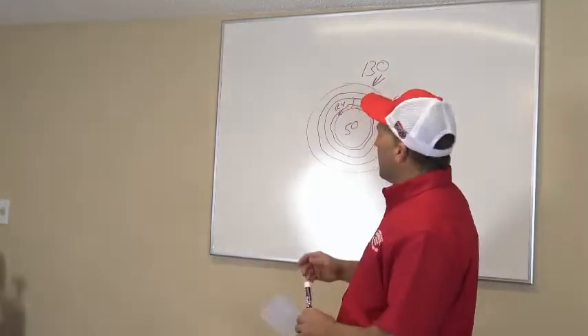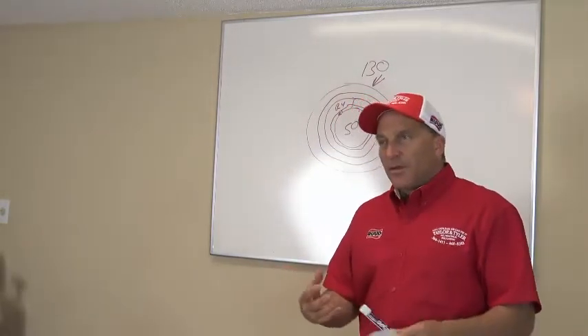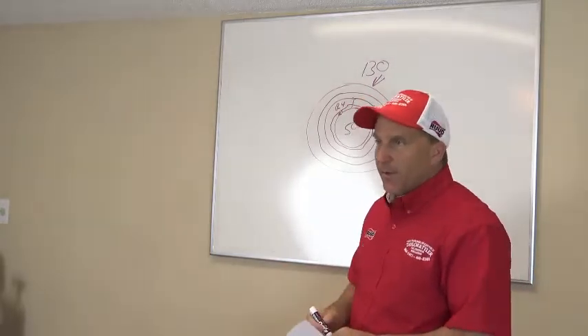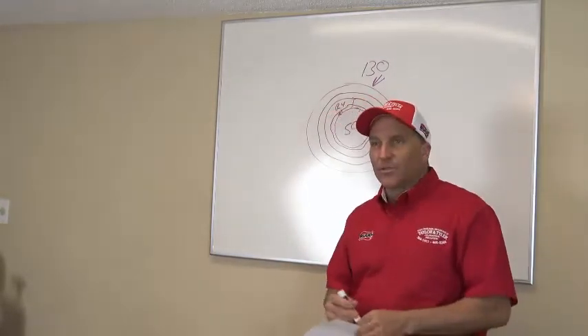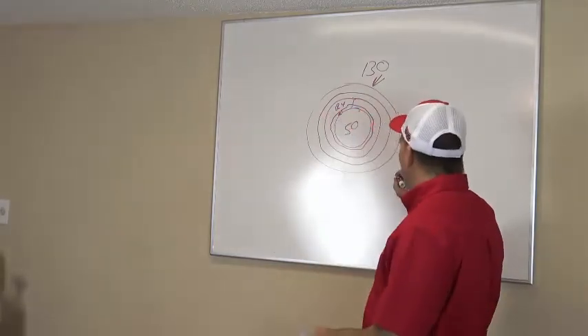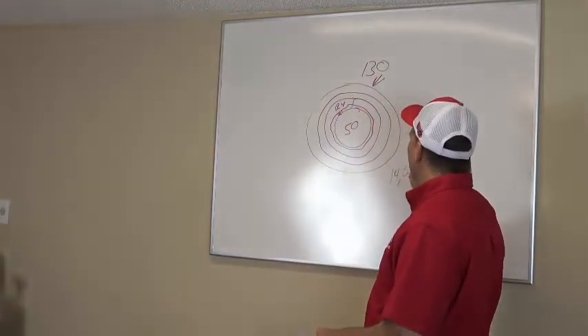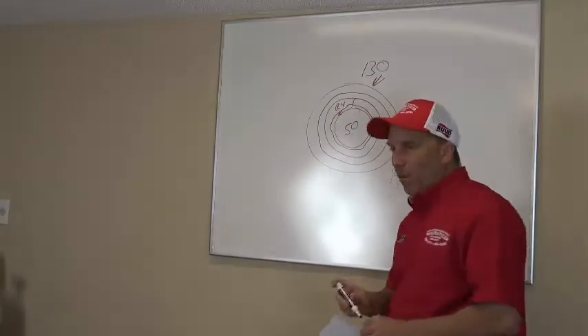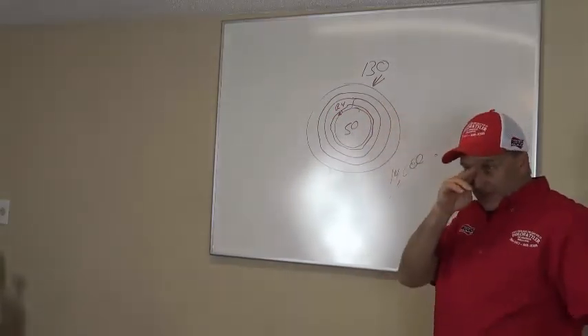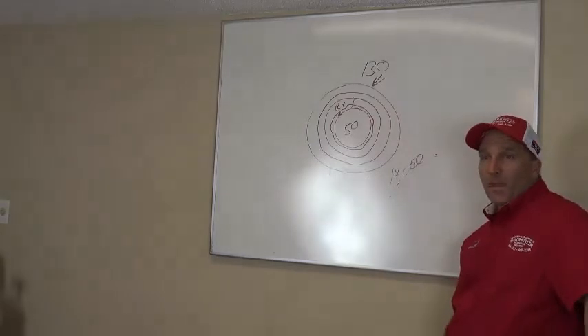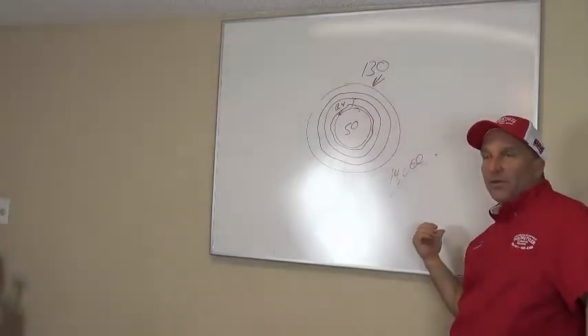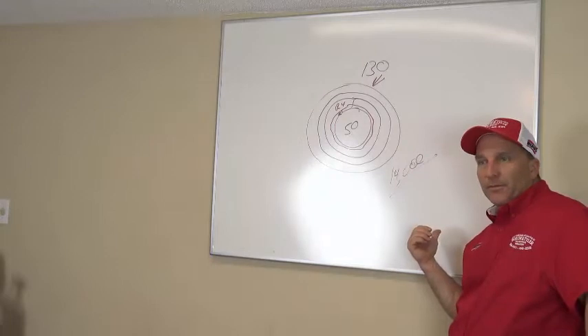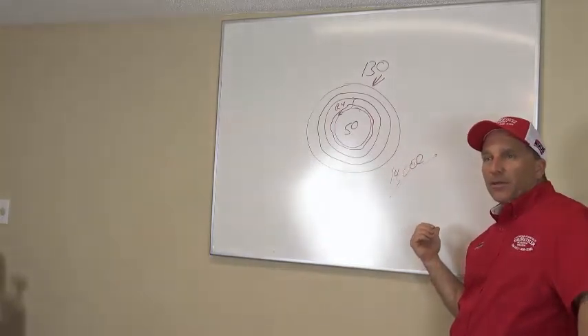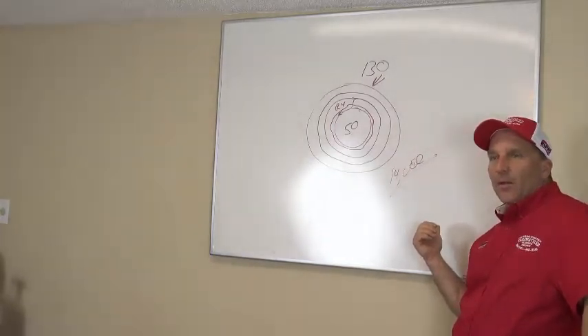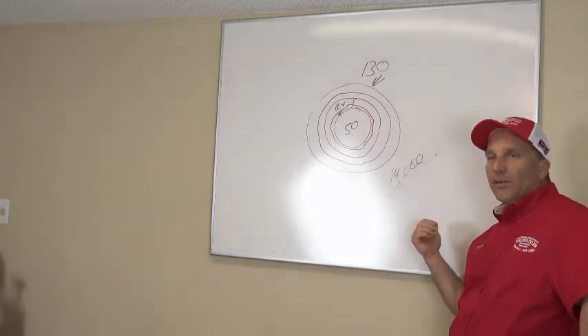Okay. Here are some true numbers. They're not exact, but they're close, okay? On a 1,500 square foot house, it takes approximately 14,000 BTUs to cool your ductwork. How many BTUs is 14,000 BTUs in tonnage? 1 ton of air is 12,000 BTUs, right? So I'm using over 1 ton of air conditioning to cool my ductwork and 2 tons to cool my house.